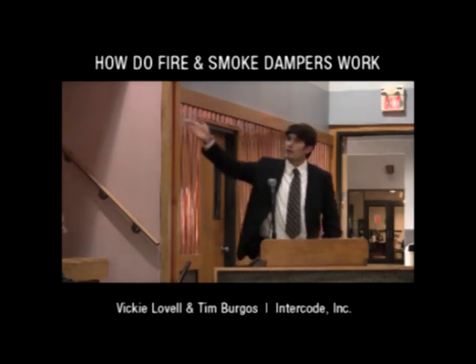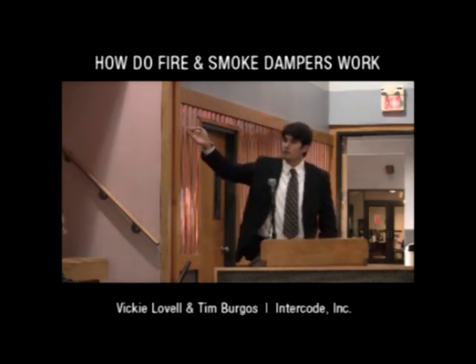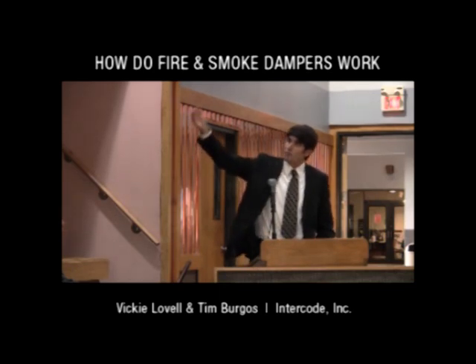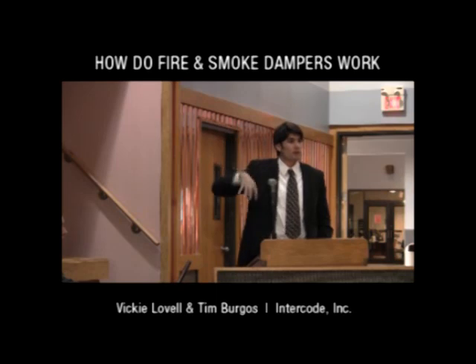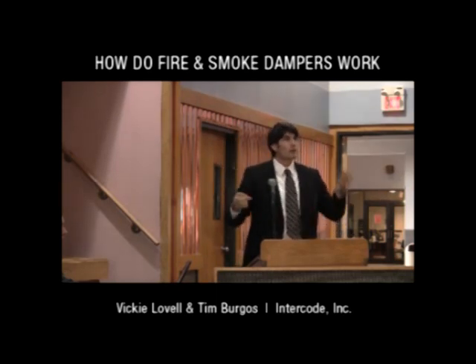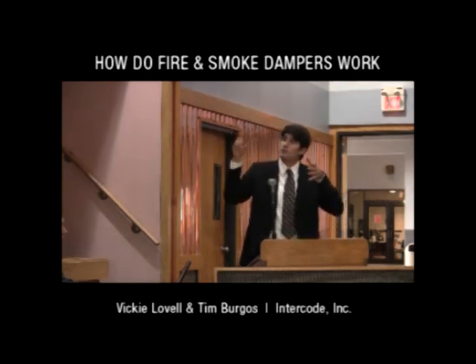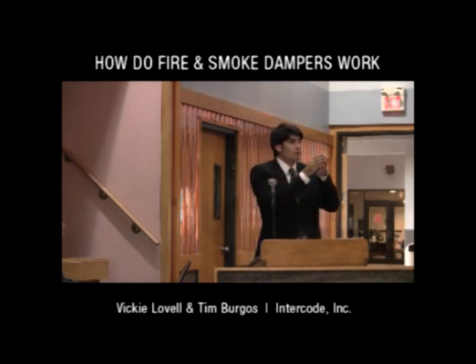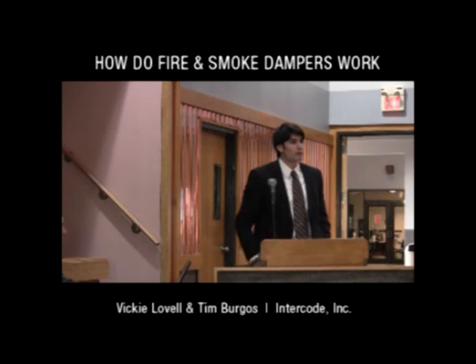And on the other side, you can see a ceiling radiation damper. It works the same way. On the top part of the dome is an actual fusible link. So when there's a fire inside a room, the fusible link will melt, causing the damper to close off the spread of flame through the HVAC system.